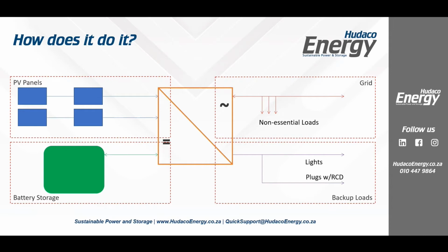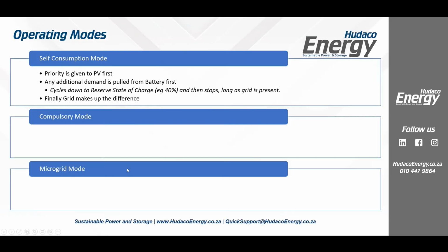Some of the systems can't do that. Some of your higher end systems do that. We have reserve state of charge, is what we call it, and that's for how much battery we reserve for load shedding conditions. And then finally, grid will make up the difference. So PV first, then batteries down to our reserve state of charge setting while grid is present. Of course, when grid falls away, so does this limit. And then finally, grid makes up the difference.